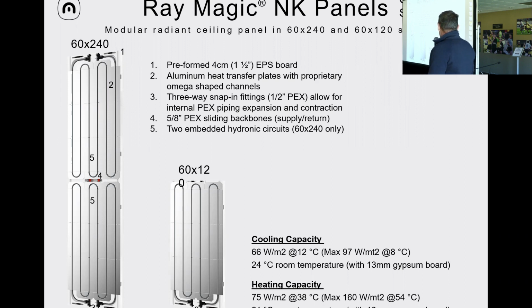In heating, there are no limitations, meaning that we can go really high temperature, and with 54 degrees we can reach up to 160 watts per square meter. Regularly, we will go low temperature to optimize the performance of the heat pump. So with 38 degrees, we can still get 75 watts per active surface with a 21 degree room temperature.